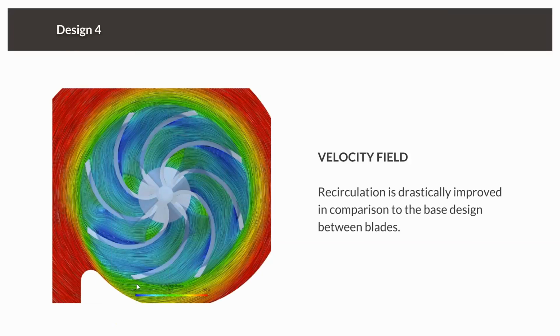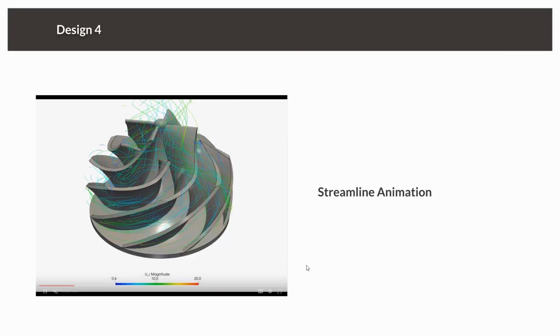And if we take a look at the other plane, you can see that the recirculation actually drastically improved in comparison to the base design between the blades, but still, the areas around the housing seem not to be perfect. And we can also create very nice animations. So in this case, you can see how the streamlines are traveling through the impeller and through the pump.